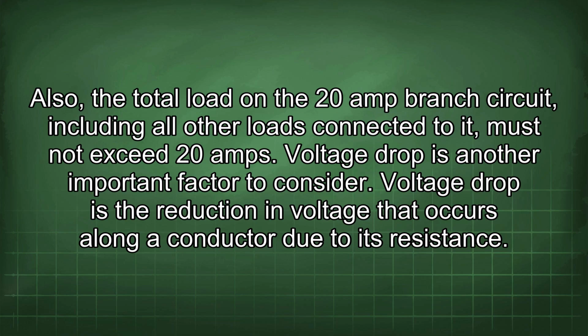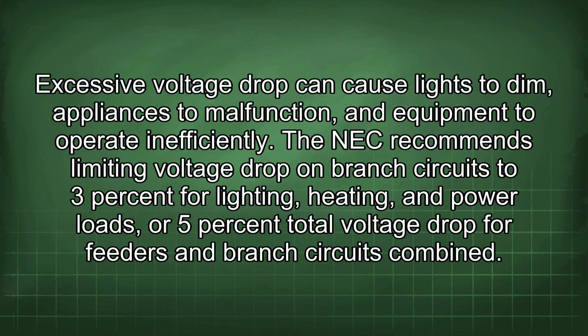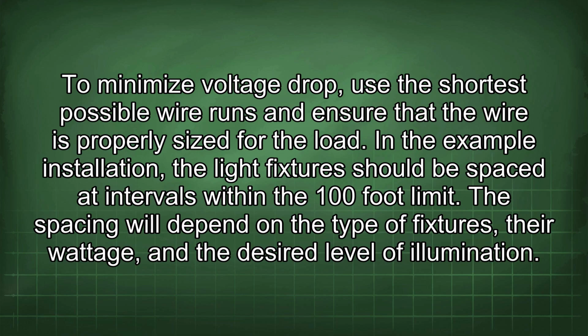Voltage drop is another important factor to consider. Voltage drop is the reduction in voltage that occurs along a conductor due to its resistance. Excessive voltage drop can cause lights to dim, appliances to malfunction, and equipment to operate inefficiently. The NEC recommends limiting voltage drop on branch circuits to 3% for lighting, heating, and power loads, or 5% total voltage drop for feeders and branch circuits combined. To minimize voltage drop, use the shortest possible wire runs and ensure that the wire is properly sized for the load.